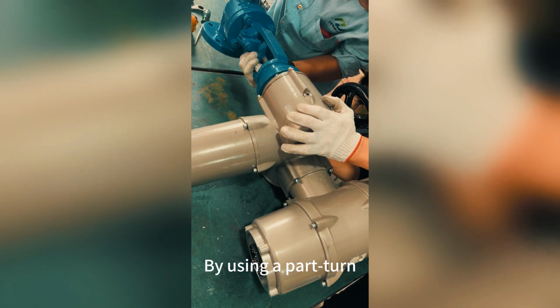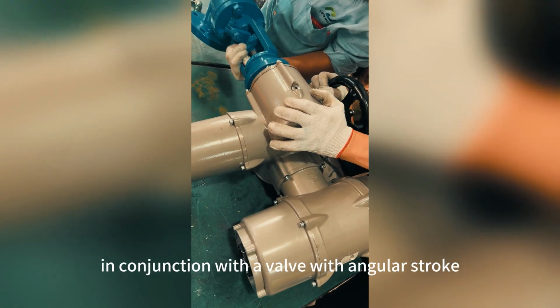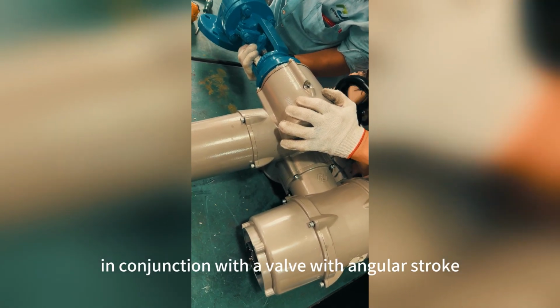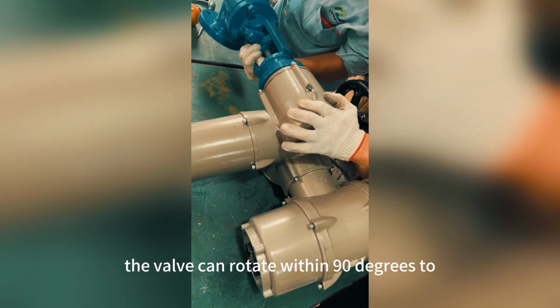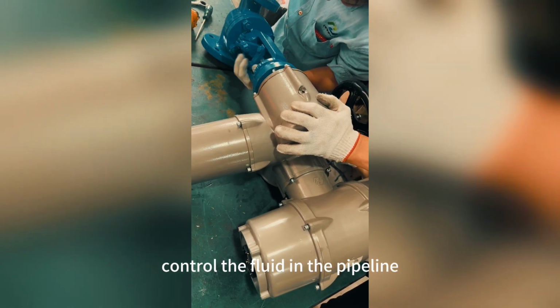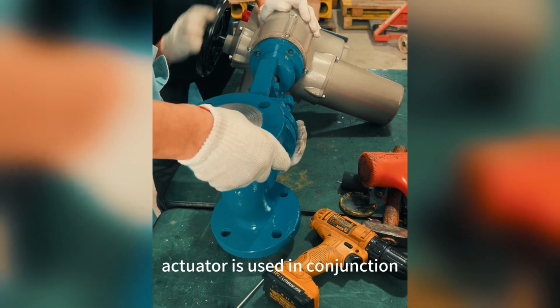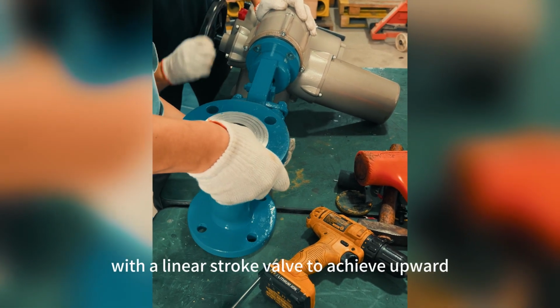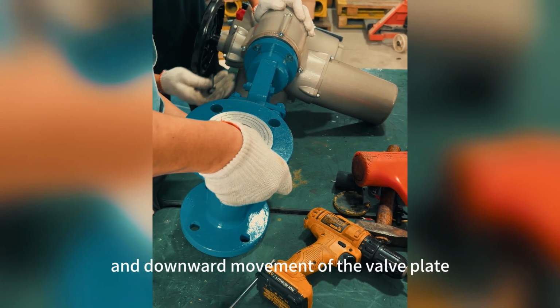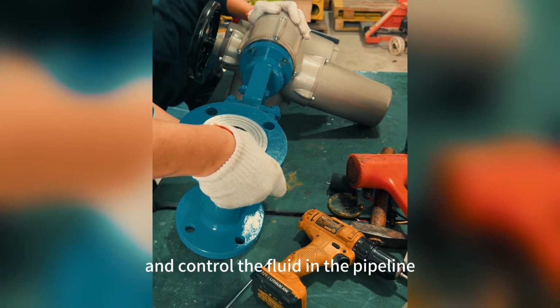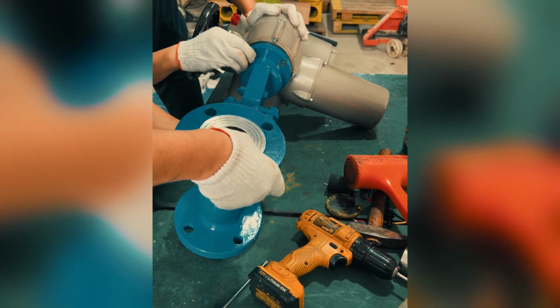By using a part-turn electric actuator in conjunction with a valve with angular stroke, the valve can rotate within 90 degrees to control the fluid in the pipeline. A linear electric actuator is used in conjunction with a linear stroke valve to achieve upward and downward movement of the valve plate, and control the fluid in the pipeline.